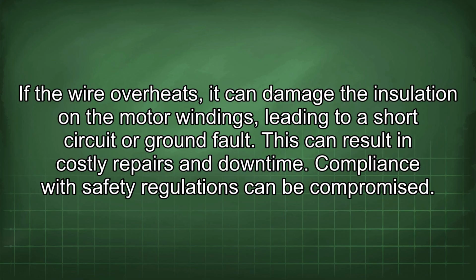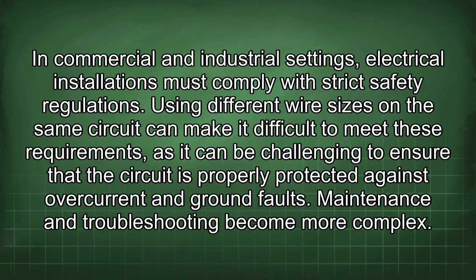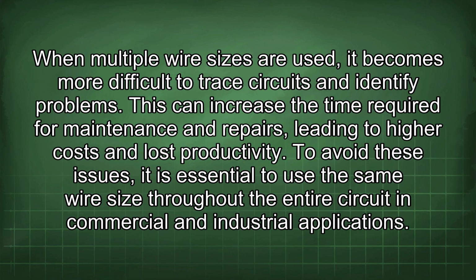Compliance with safety regulations can be compromised. In commercial and industrial settings, electrical installations must comply with strict safety regulations. Using different wire sizes in the same circuit can make it difficult to meet these requirements, as it can be challenging to ensure that the circuit is properly protected against overcurrent and ground faults. Maintenance and troubleshooting become more complex. When multiple wire sizes are used, it becomes more difficult to trace circuits and identify problems. This can increase the time required for maintenance and repairs, leading to higher costs and lost productivity.